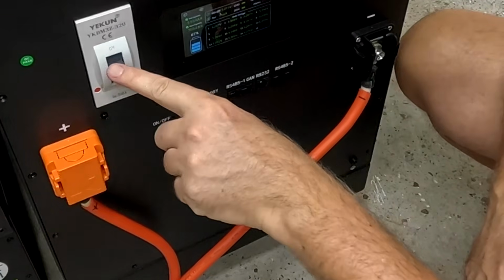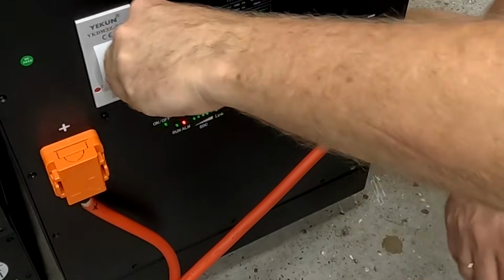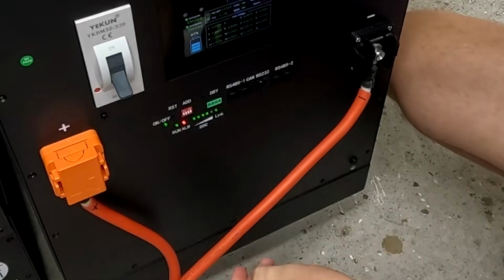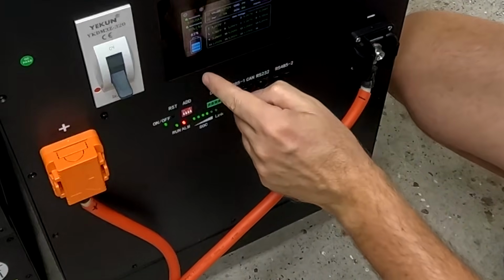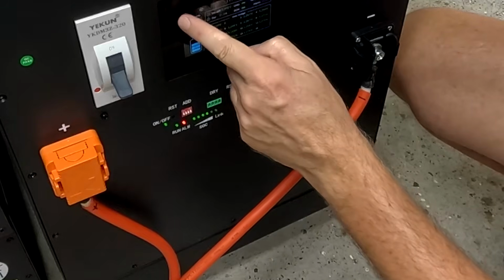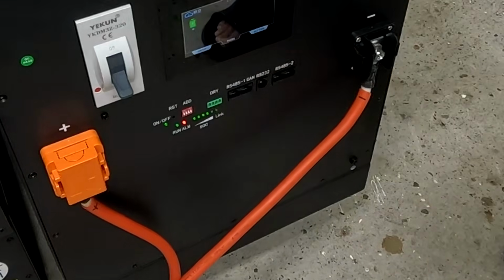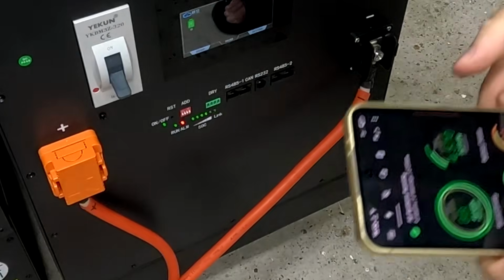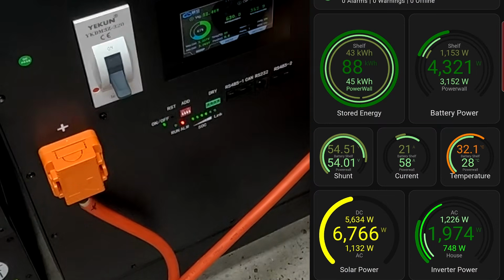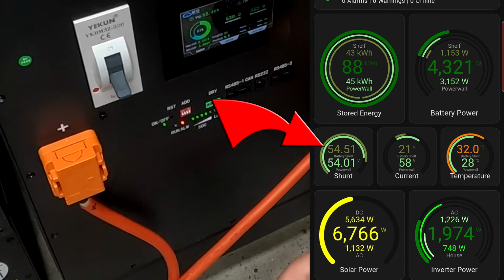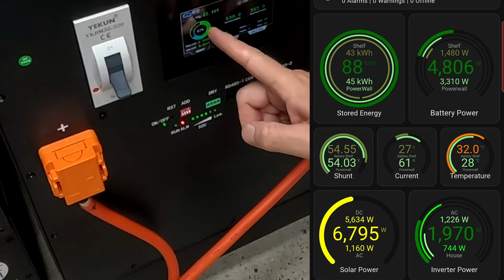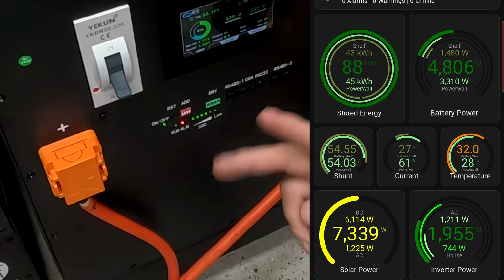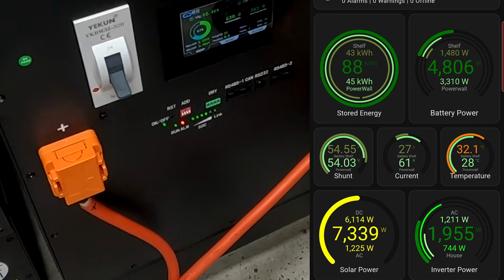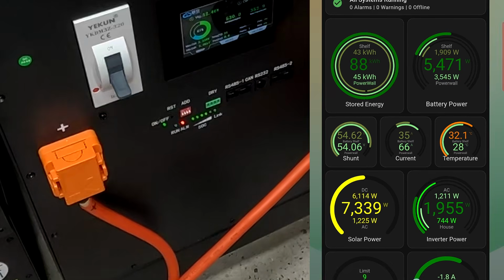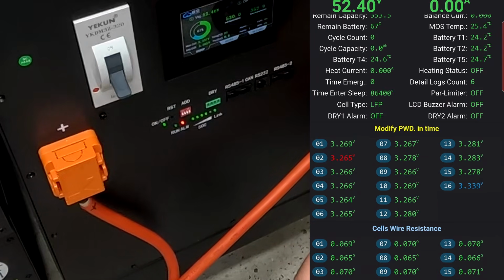Alright, so if I turn this one off... come on, it's off now, and back on, we will have an inrush current here into the BMS. Probably should set a maximum charge current. The battery shelf sits on 54.5 volts, so close to 100% charged, and this one is at 52.4 volts, so there's 2 volt difference. It shouldn't be too bad, but again, I just want to make sure.